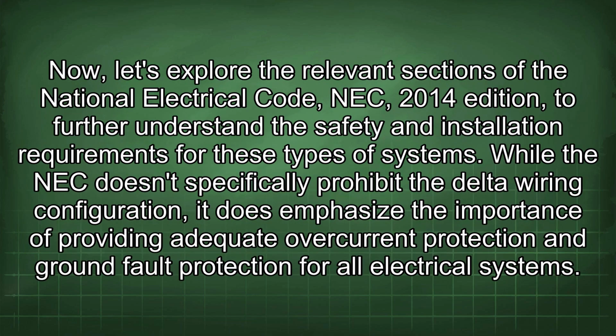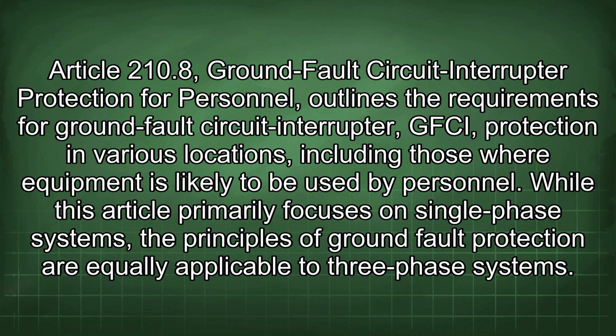Now, let's explore the relevant sections of the National Electrical Code, NEC 2014 edition, to further understand the safety and installation requirements for these types of systems. While the NEC doesn't specifically prohibit the delta wiring configuration, it does emphasize the importance of providing adequate overcurrent protection and ground fault protection for all electrical systems. Article 210.8 Ground Fault Circuit Interrupter Protection for Personnel outlines the requirements for ground fault circuit interrupter (GFCI) protection in various locations, including those where equipment is likely to be used by personnel. While this article primarily focuses on single-phase systems, the principles of ground fault protection are equally applicable to three-phase systems.